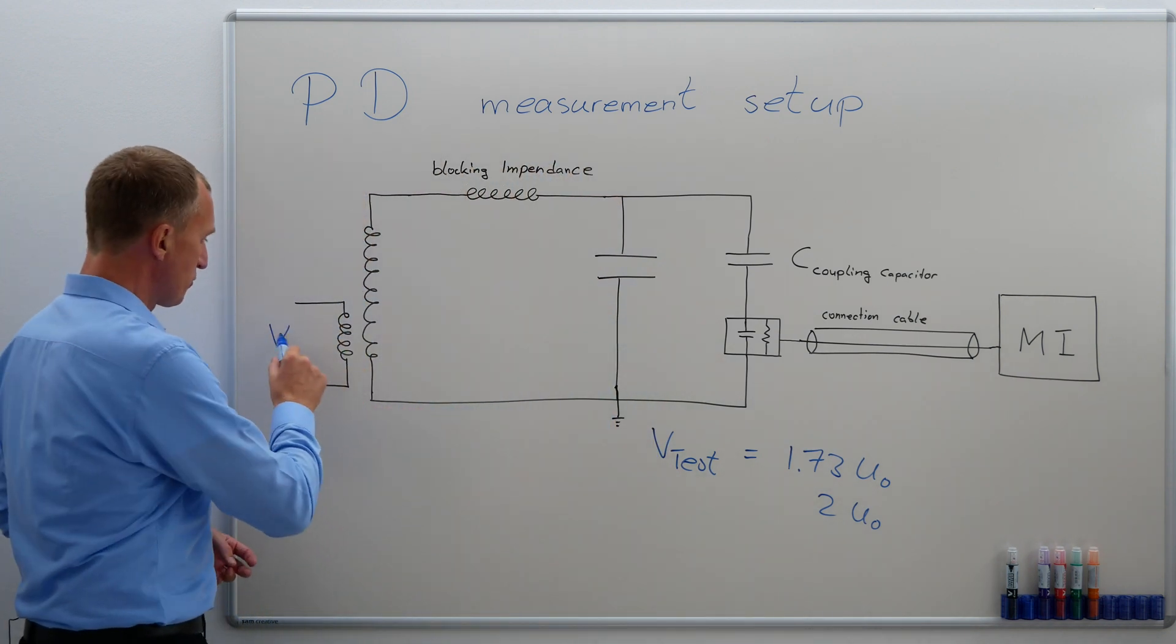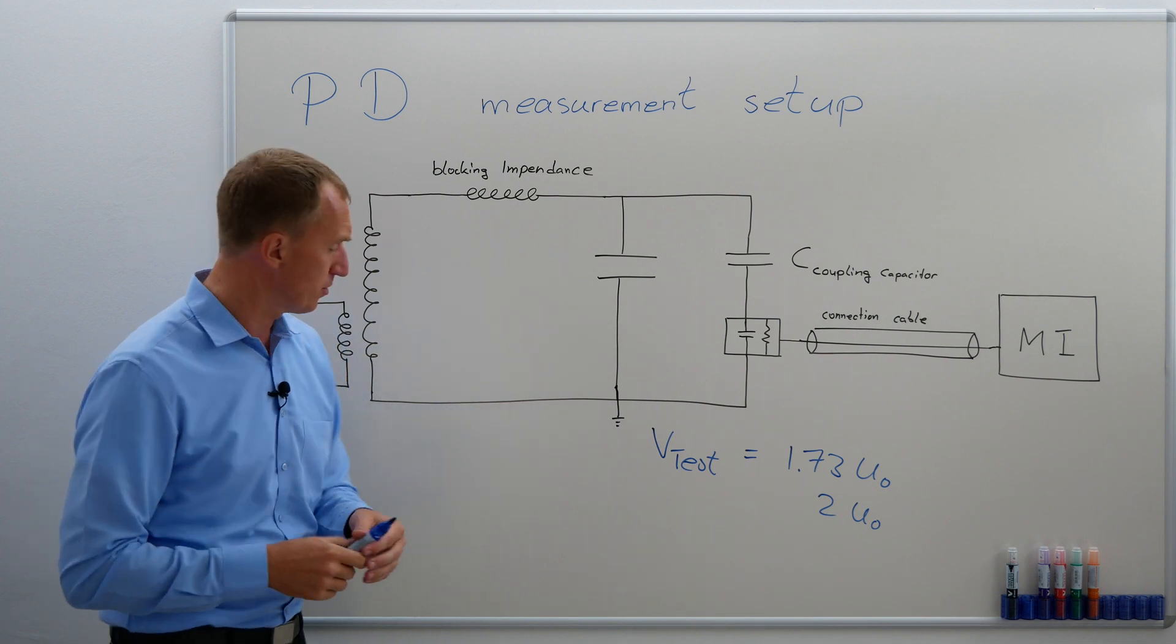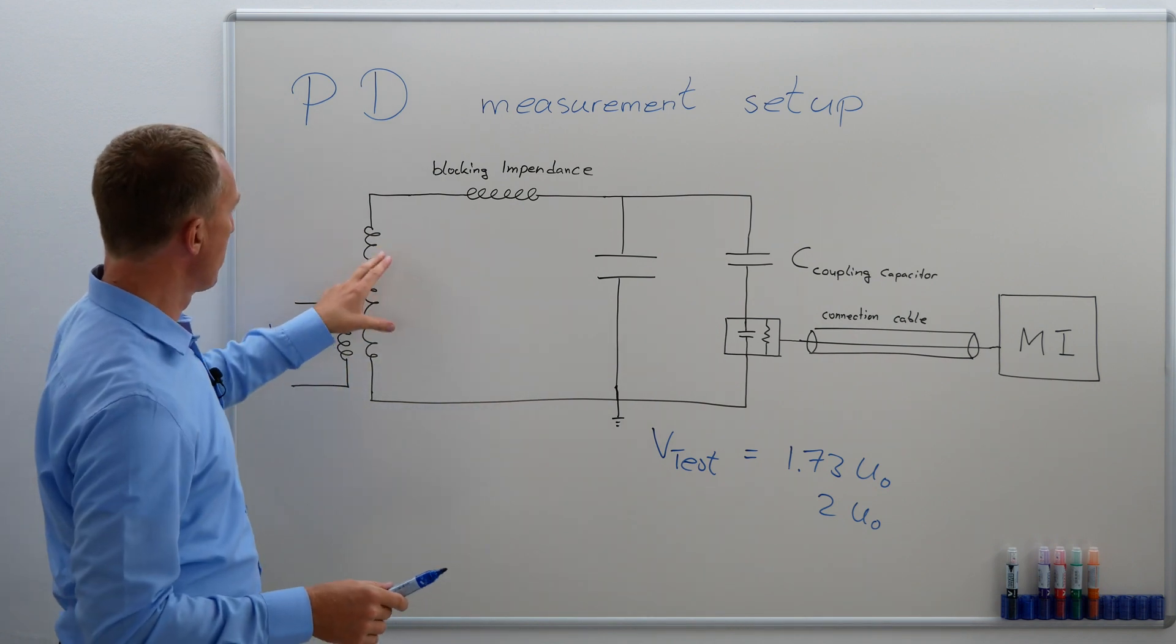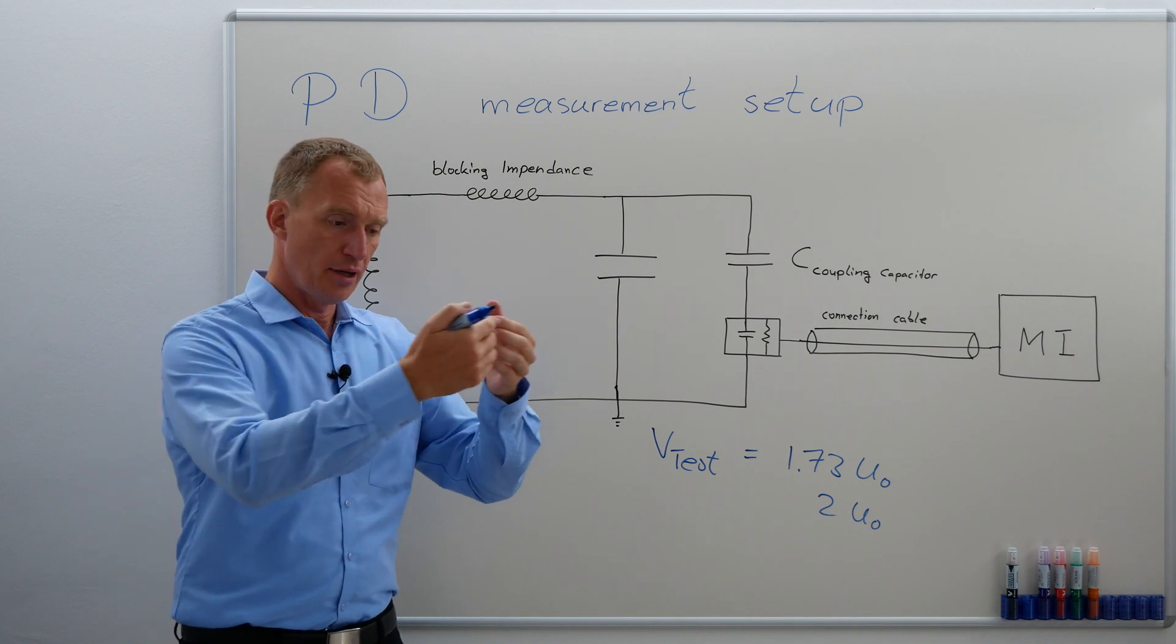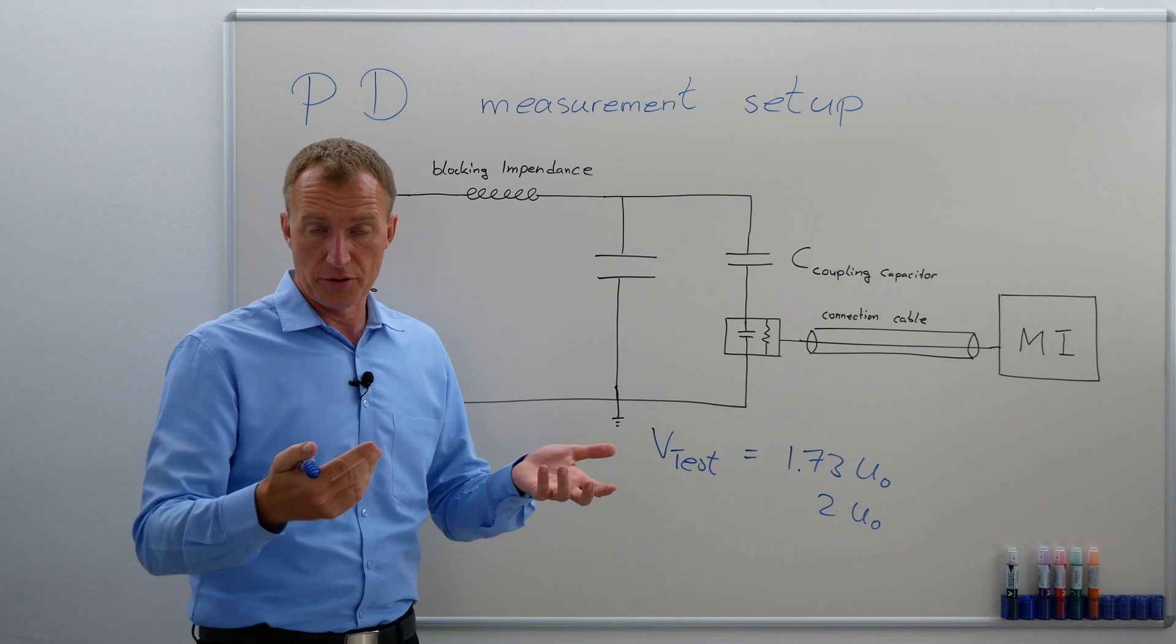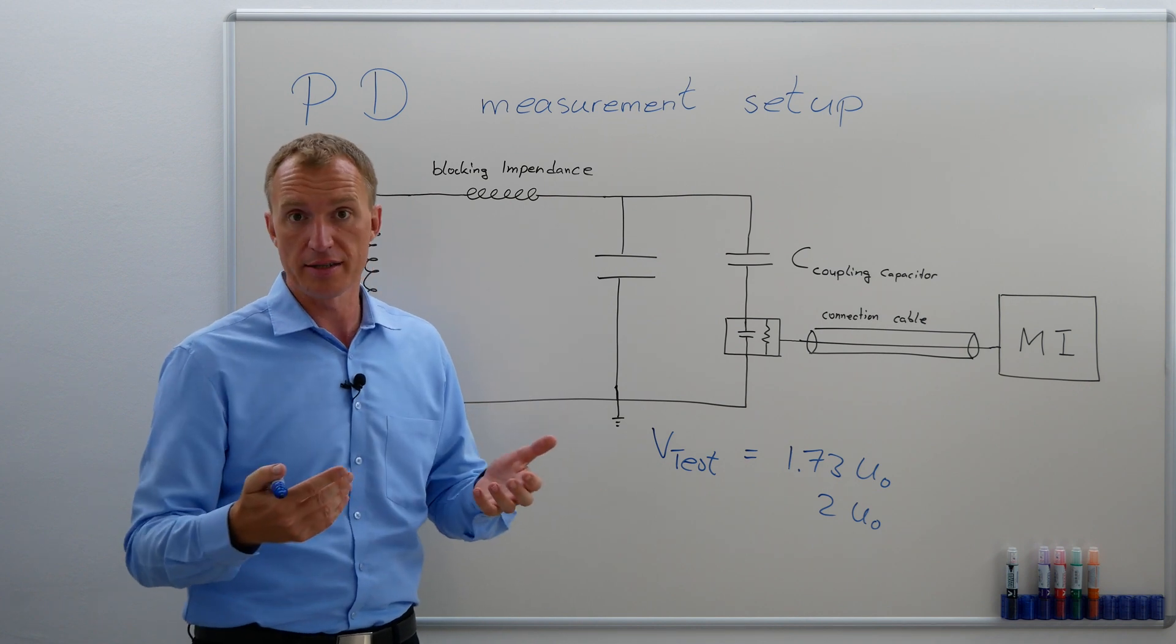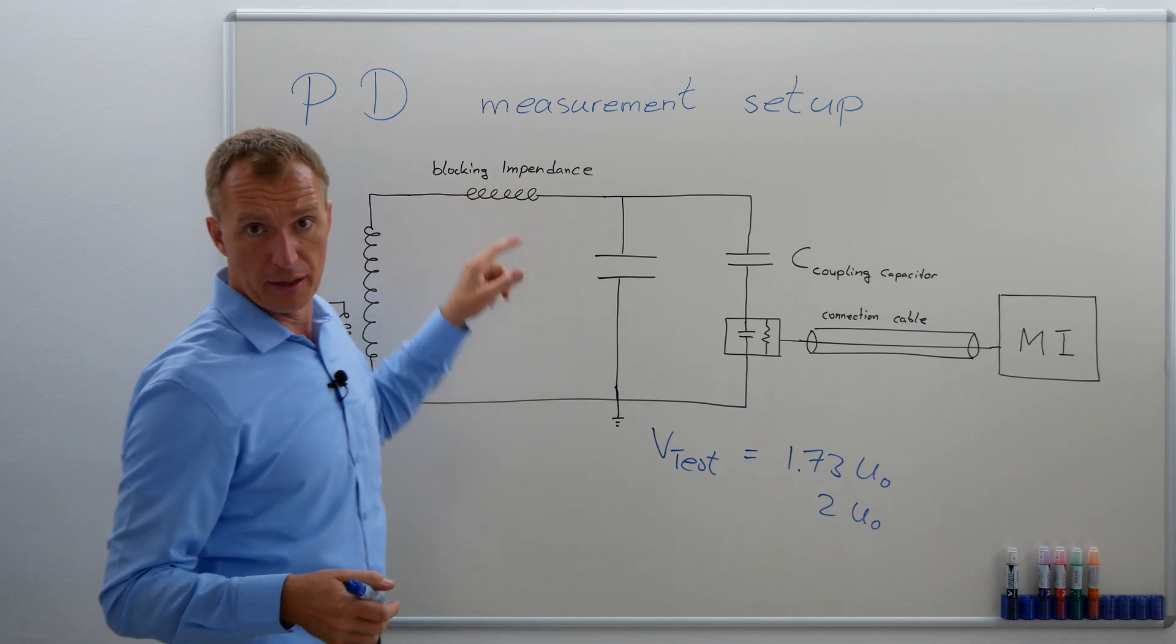Therefore, we need a regulating transformer that we can regulate. The transformer usually gets something between 110 or 400 volts. The transformer itself could transmit noise coming from the energy network, or the transformer itself could have partial discharges. So it's a very clever idea to put a blocking impedance in there.